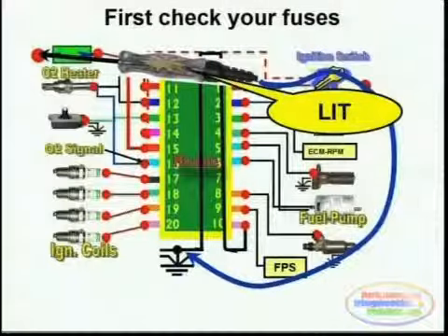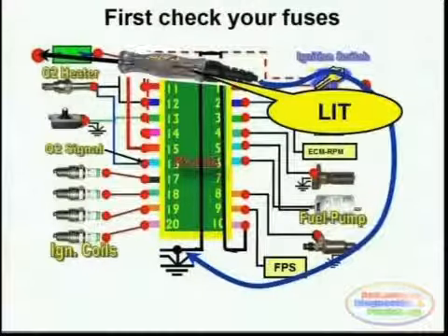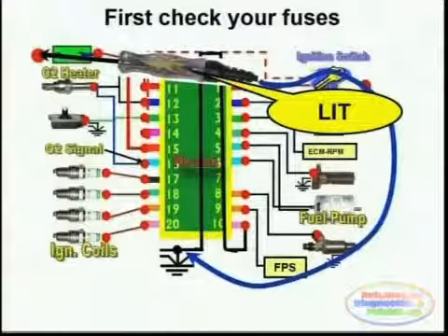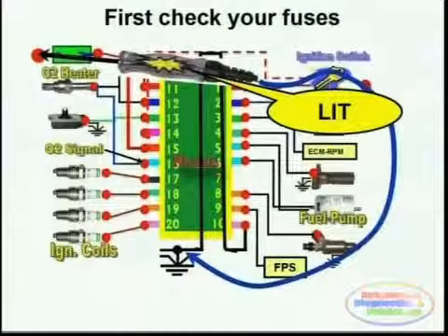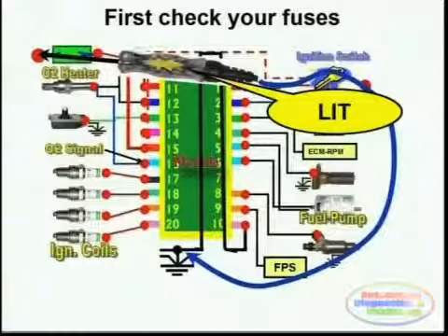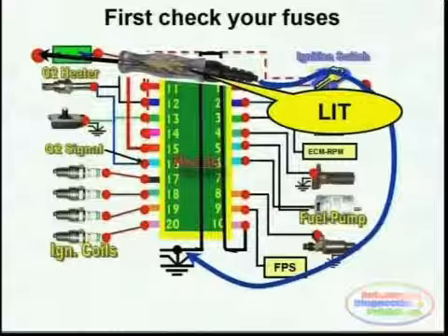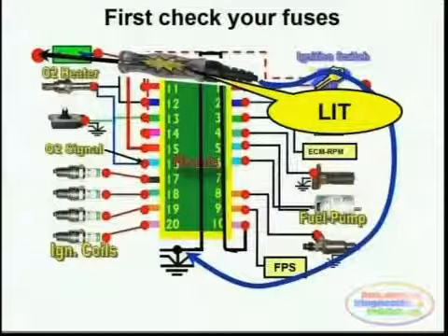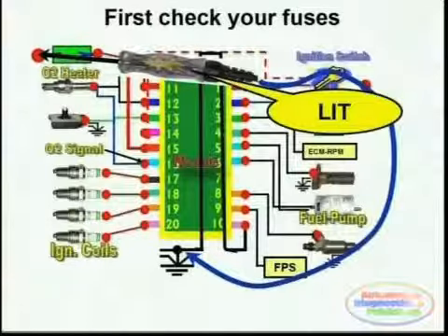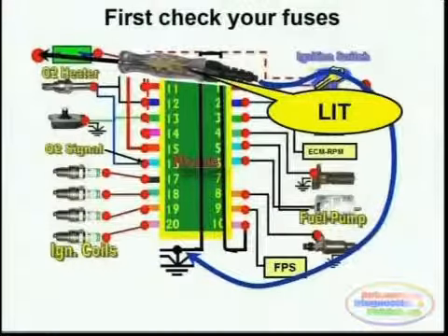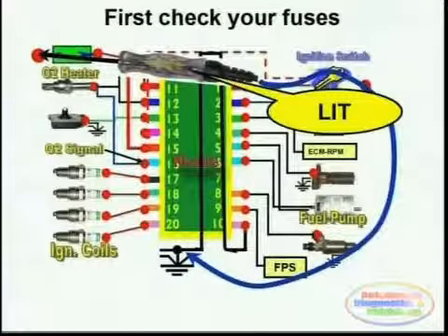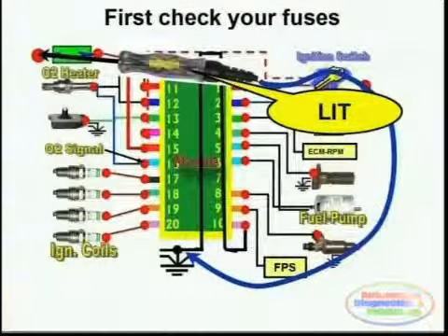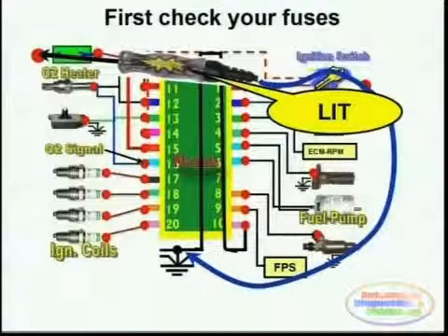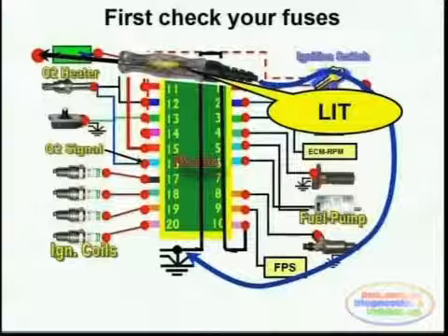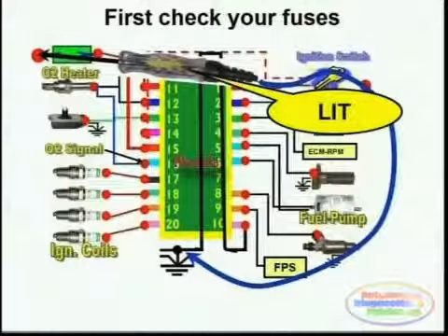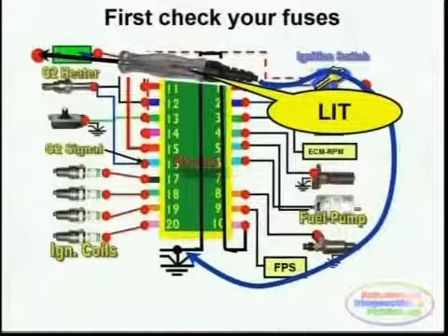This may sound simplistic and even dumb, but many times a technician forgets to check the other side of the fuse, simply finds a popped fuse, and immediately starts hunting for a short. Remember that you need supply voltage on the other side of the fuse, and your problem may lie somewhere else. For the fuse to pop, you will more than likely have a short on the circuit side of the fuse, but it's always a good idea to check your supply voltage going into the circuit itself.